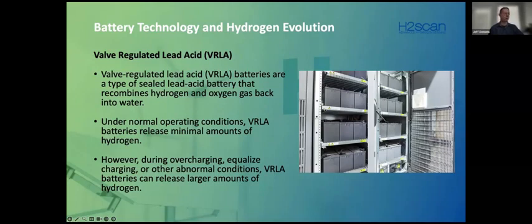All the water goes back into the battery, into the absorbed glass mat located between the plates. However, if you do a boost or equalized charge where you're increasing the charge voltage, which a lot of times you have to do in order to equalize cell voltages, then as soon as the pressure inside the battery reaches above, say, 5 psi, the valve can open and release hydrogen. We try not to do this on a regular basis. If anybody likes to hit the equalize button, it's not a good practice unless you have a reason to do so. But anytime you do that, you have a potential for hydrogen to be released into the atmosphere. That happens during what we call overcharging or equalized charging.